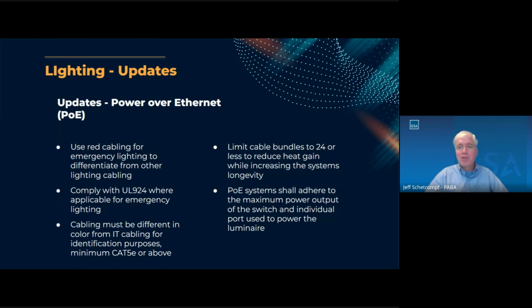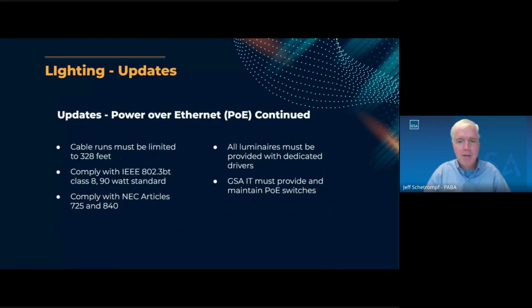So we also have the system should not exceed the power output for both the switch and the actual port used to power the luminaires. That's something to watch out for on the designs, as you could inadvertently exceed the switch limits. So the cable length, that's pretty standard for Ethernet cable, the 328 feet there.